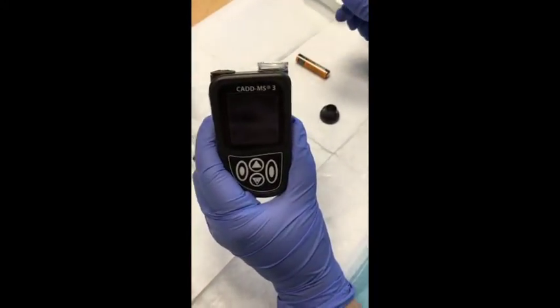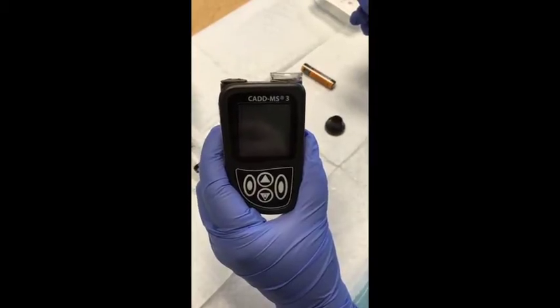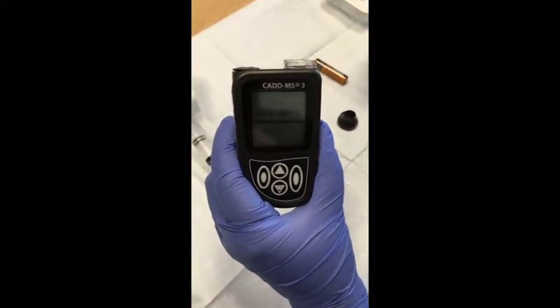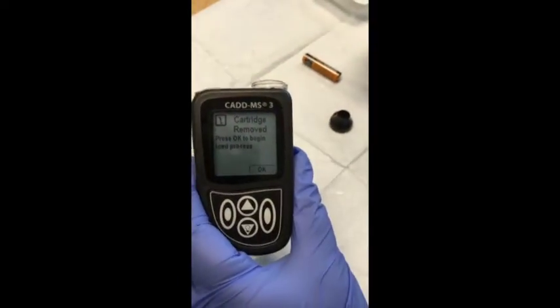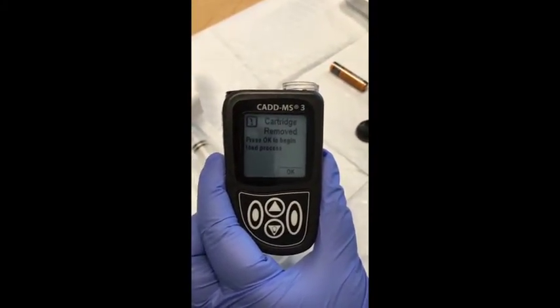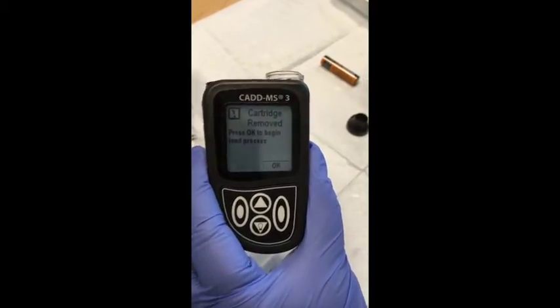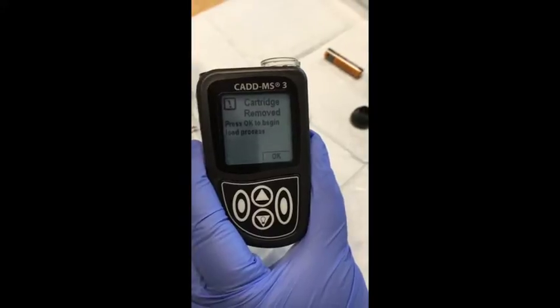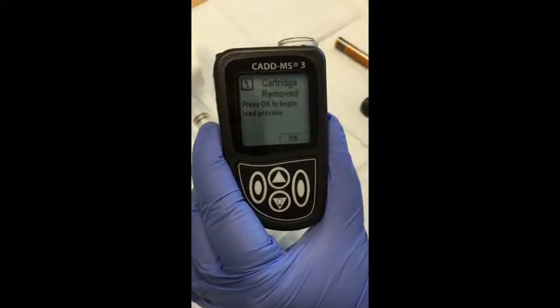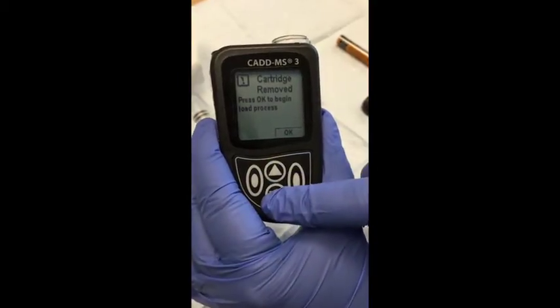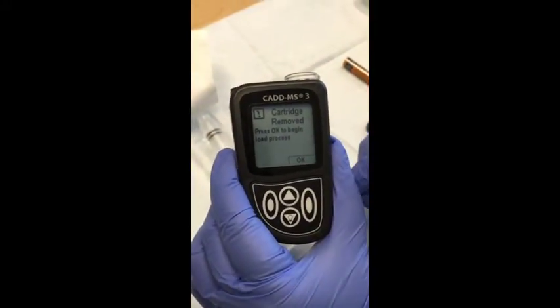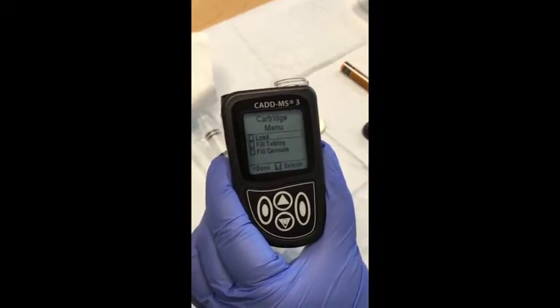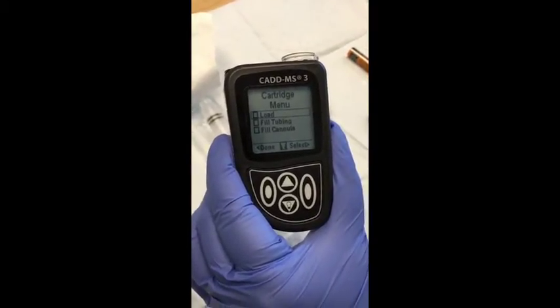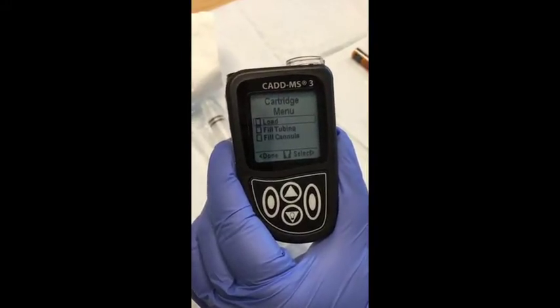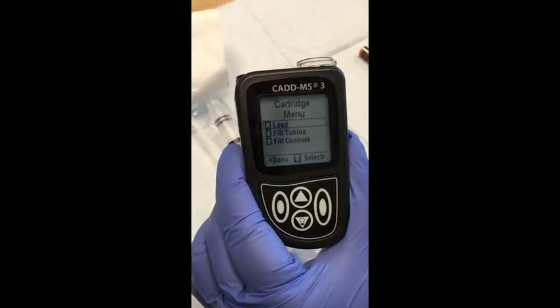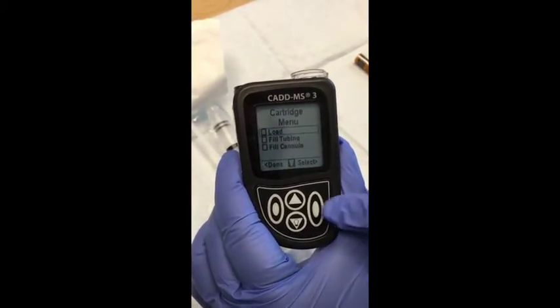Once it's tightened completely, just wait until the pump turns on. The pump will alert that the cartridge is removed and prompt you to begin the loading process, and the pump will give you directions. Just remember, it is not a touch screen, so you have to use the up and down arrows and the buttons on the bottom. So go ahead and press OK. It says cartridge menu: load, fill tubing, and fill cannula. We'll only be using load and fill tubing. We will not use fill cannula. So go ahead and select load.